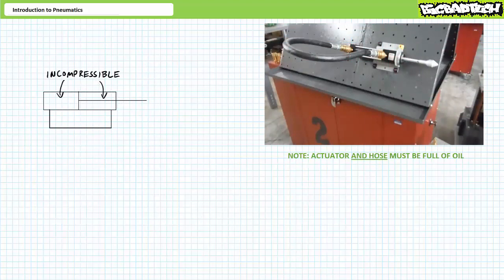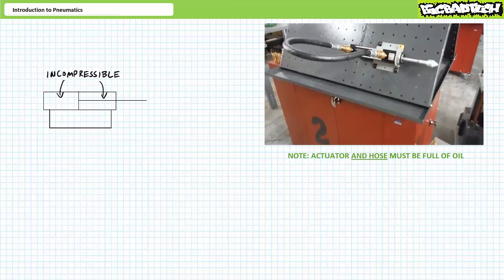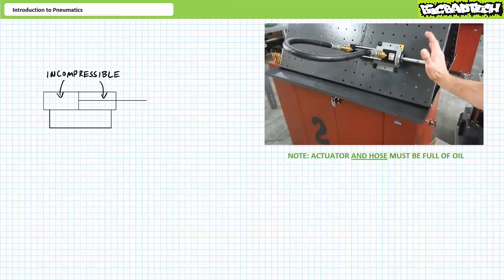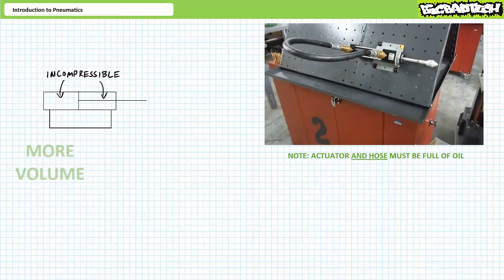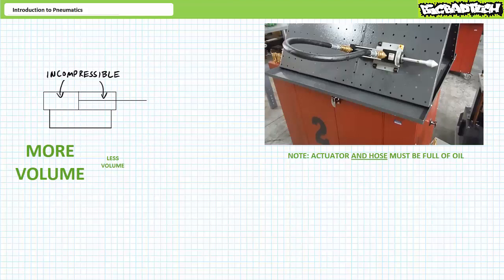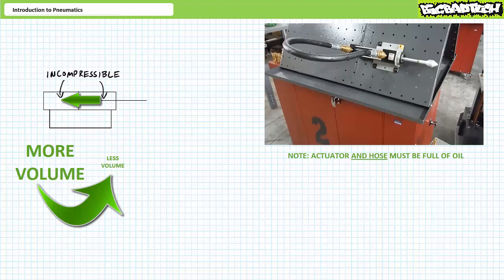Here's yet another example of the differences between liquid and gas-based fluid power systems. Consider a partially extended double-acting hydraulic cylinder filled with incompressible oil. If I hook the rod end to the cap end, can an external force push the rod back in? The answer is no. The cap end contains more volume, rod end less. The act of retraction necessitates that the larger cap end volume be stuffed into the smaller rod end volume.